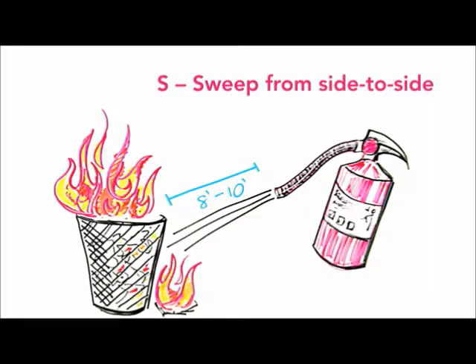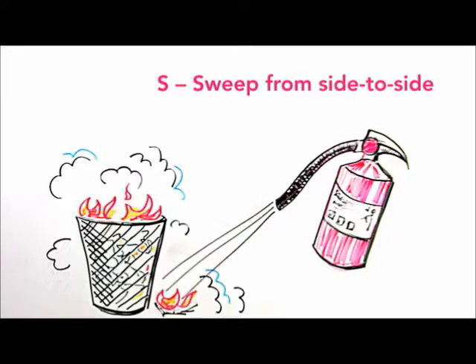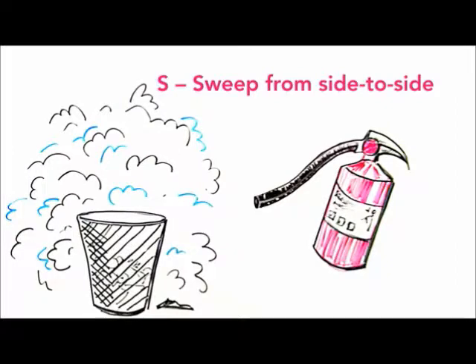Maintain your distance from the fire and sweep the nozzle from side to side, sweeping 3 to 6 inches beyond the right and left edges of the fire. Discharge the extinguisher until contents are exhausted to prevent re-ignition. Move around the fire to confirm it is completely extinguished.